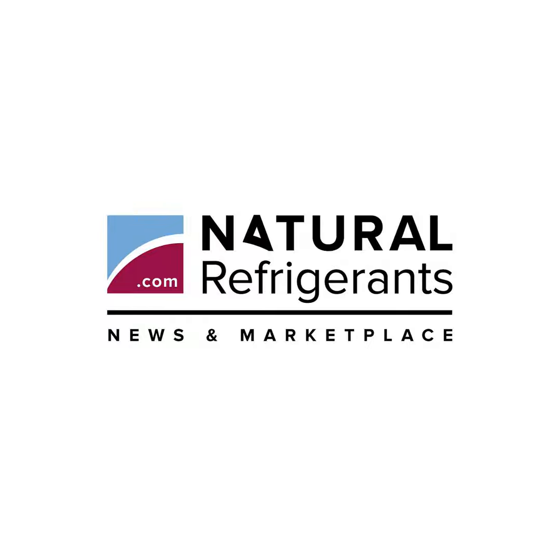CERN and sustainability. CERN won the ATMO Europe 2025 Best in Sector Industrial End User Award for its use of a CO2-based refrigeration system to cool its new High Luminosity Large Hadron Collider (LHC) program, scheduled to start operating in 2030. CERN expects its new CO2 cooling system, providing a combined capacity of 1.3 megawatts, 370 tons of refrigeration, at its ATLAS and CMS particle detectors, to reduce its greenhouse gas emissions by 40,000 metric tons of CO2 per year compared to synthetic alternatives.